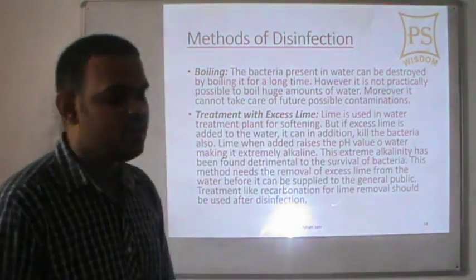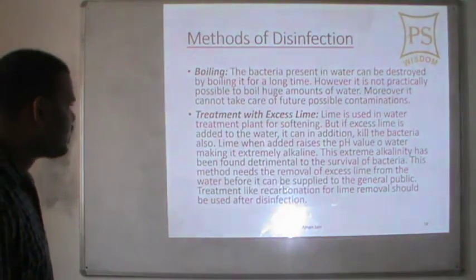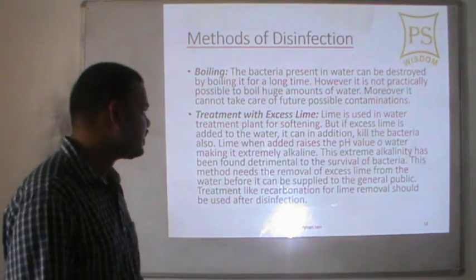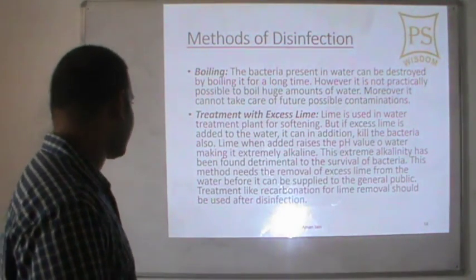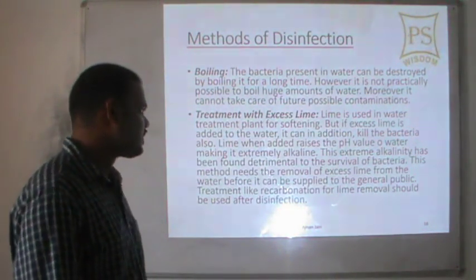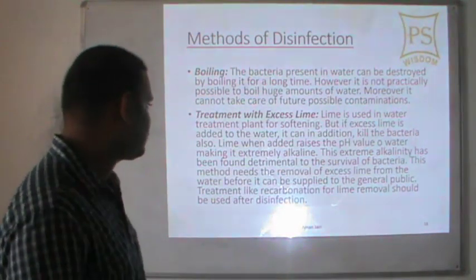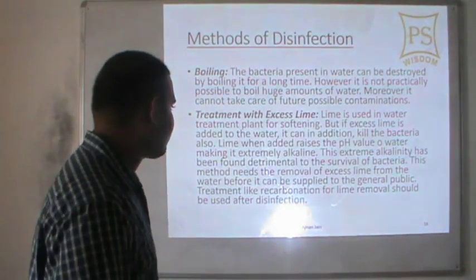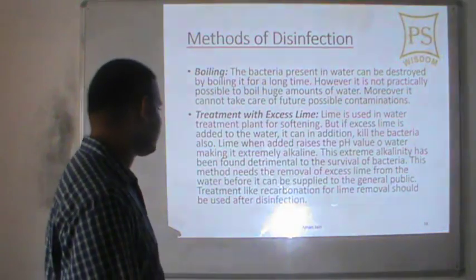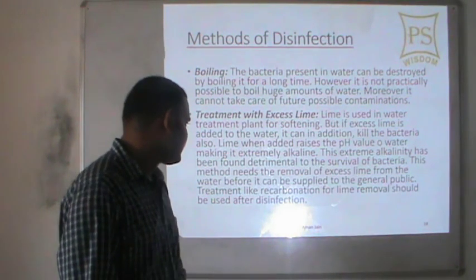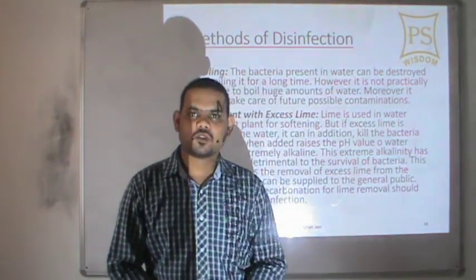Treatment with excess lime: lime is used in water treatment plants for softening, but if excess lime is added to the water, it can also kill bacteria. Lime raises the pH value of the water, making it extremely alkaline. This extreme alkalinity has been found detrimental to the survival of bacteria. However, the excess lime must be removed from the water before it is supplied to the public. Recarbonation is used for lime removal after disinfection.